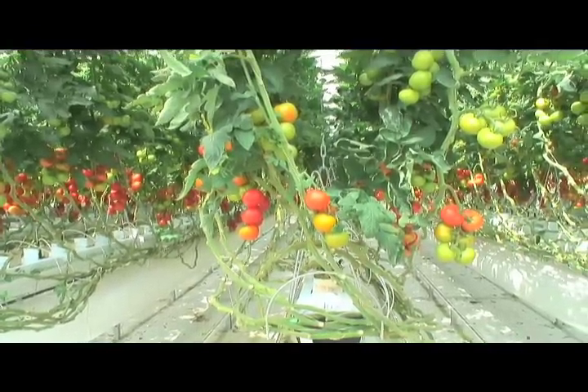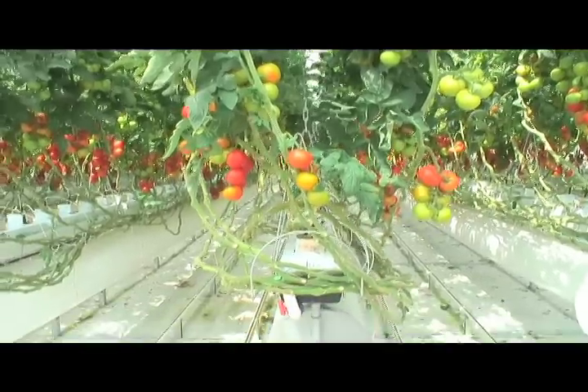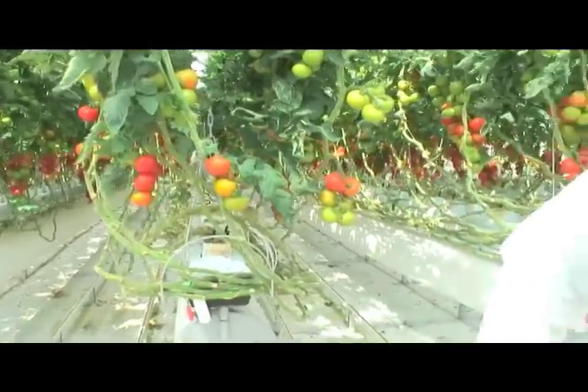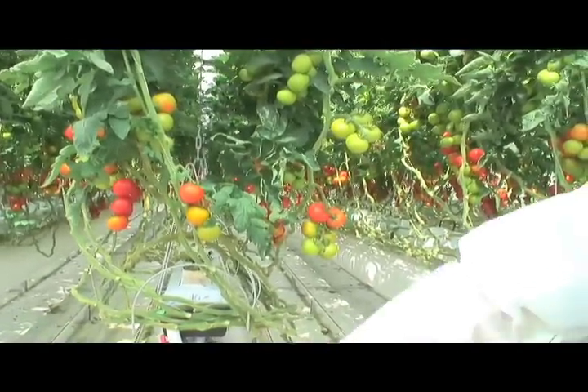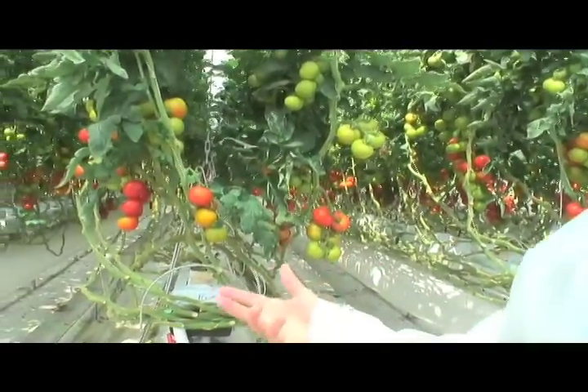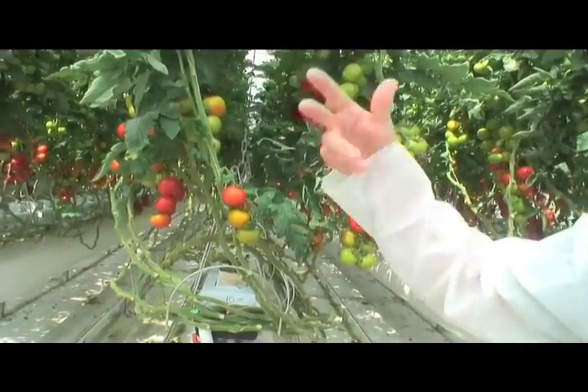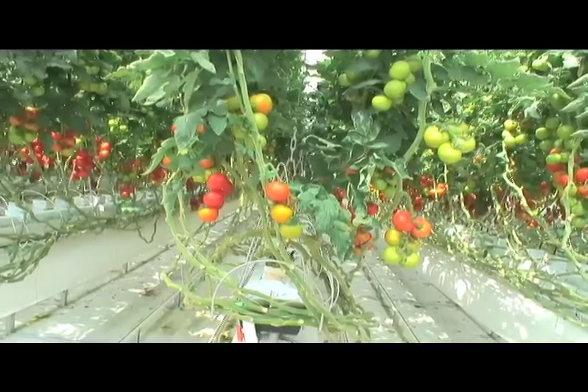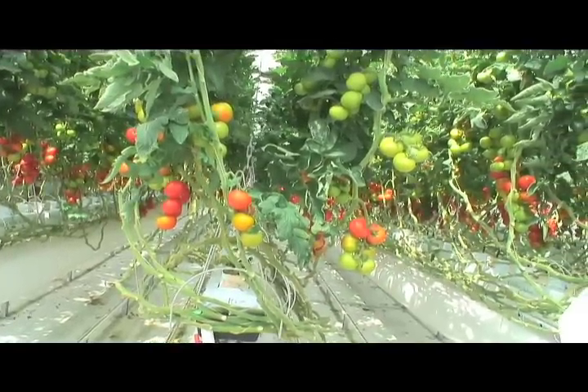With 18-20 degrees, we can put it in aquifers down the earth. In winter time we can put the 20 degrees in a heat pump, and with a heat pump you can make 40 degrees from 20 degrees, and with 40 degrees you can heat the greenhouse again. But you need a heat pump to heat this kind of greenhouse.